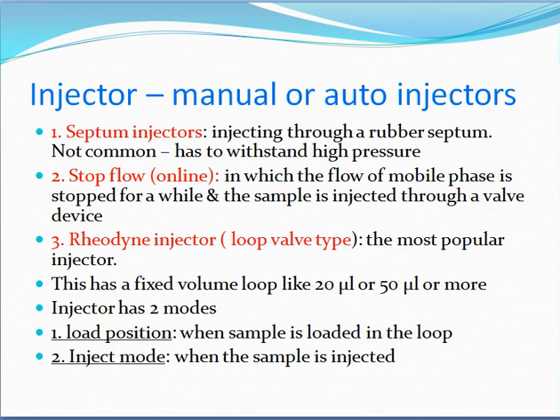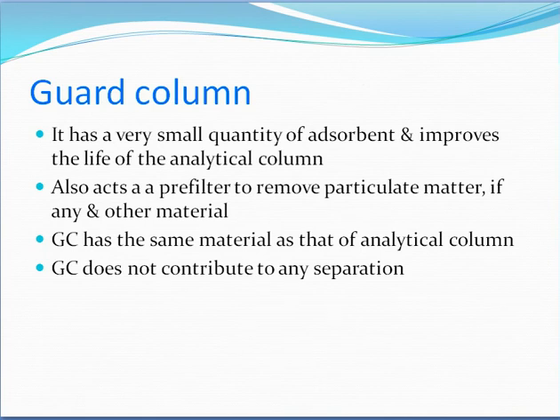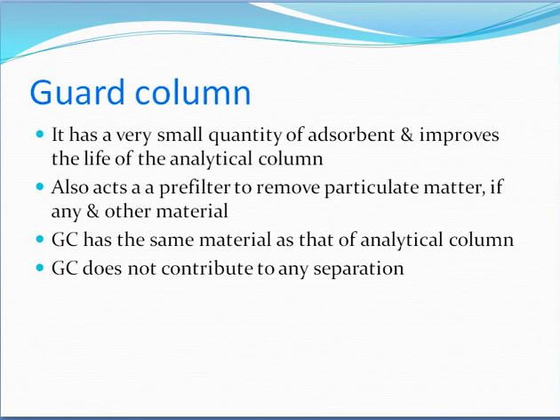The valve loop injector is the most popular type. It has a fixed volume loop, such as 20 or 50 microliters, and operates in two modes: load position, where sample is loaded into the loop, and inject mode, where the sample is injected onto the column. The guard column contains a small quantity of adsorbent, improves the life of the analytical column, and acts as a pre-filter to remove particulate matter and other interfering materials.